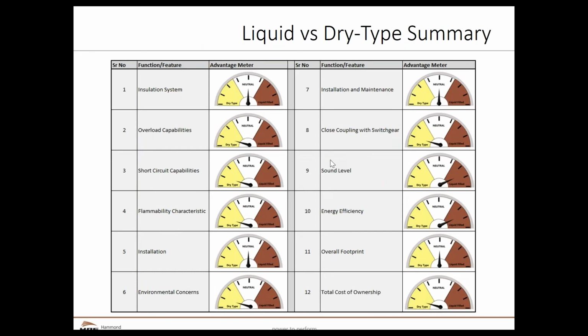So we have our cute little charts here. This kind of shows where there's neutral, where there's advantages to liquid filled, and where there's advantages to dry type transformers. Again, what we're seeing here in a lot of cases is these are typical parameters. We might be able to overcome these parameters with either design, but it may go a little bit over typical design. And some of these judgments where we got the arrow pointed, if it's better one way or another, might always have additional dependencies. So this is meant to be a quick reference chart, but how you may or may not have an advantage in your particular design will be application oriented.